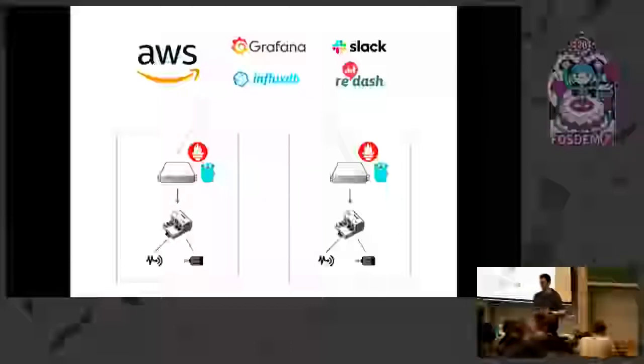So, for example, in every water pipe in the containers, we have pressure sensors. And so we can set thresholds on the values of these sensors, so we can detect when there is a huge change in water pressure. And so these changes will trigger alerts, and they might indicate that there is a leak in the hydraulic system. And so this is how we can send a plumber on site to fix it.